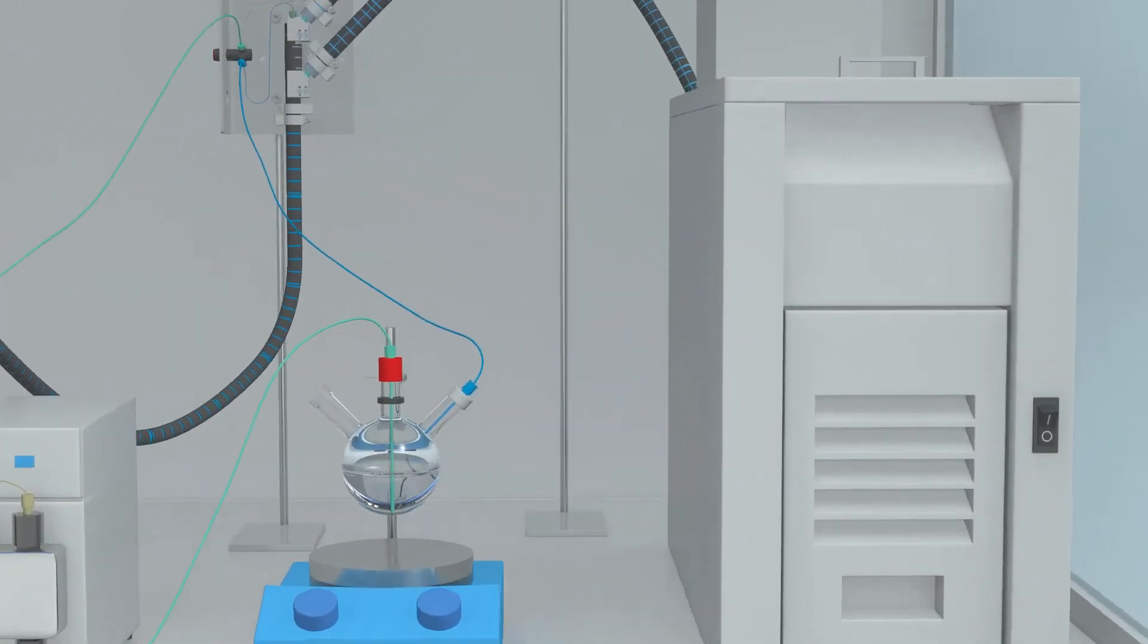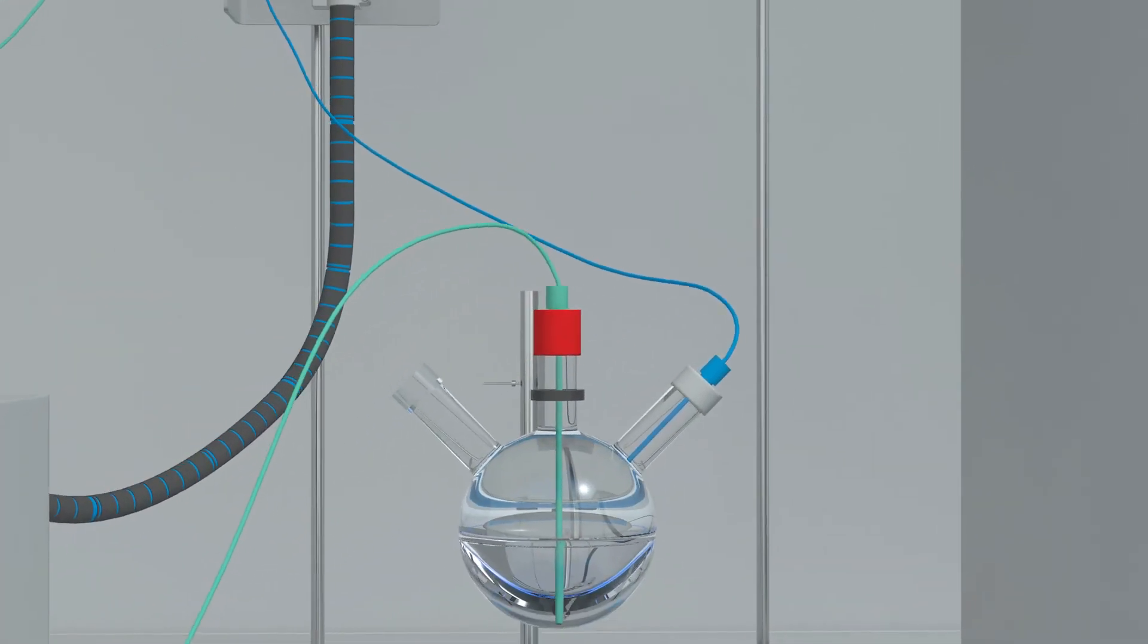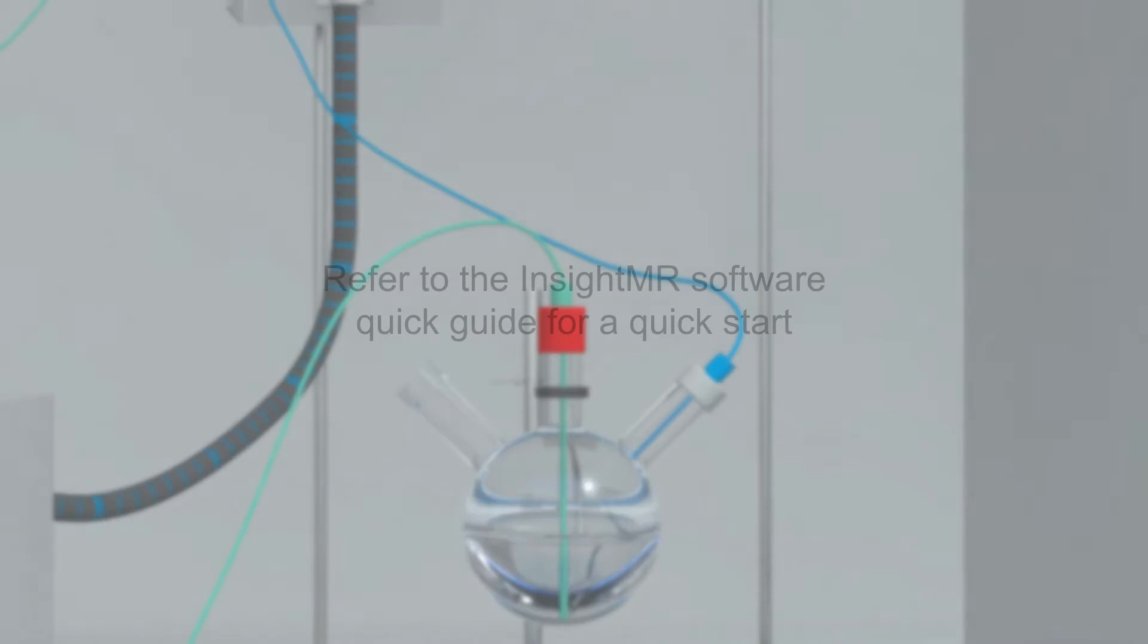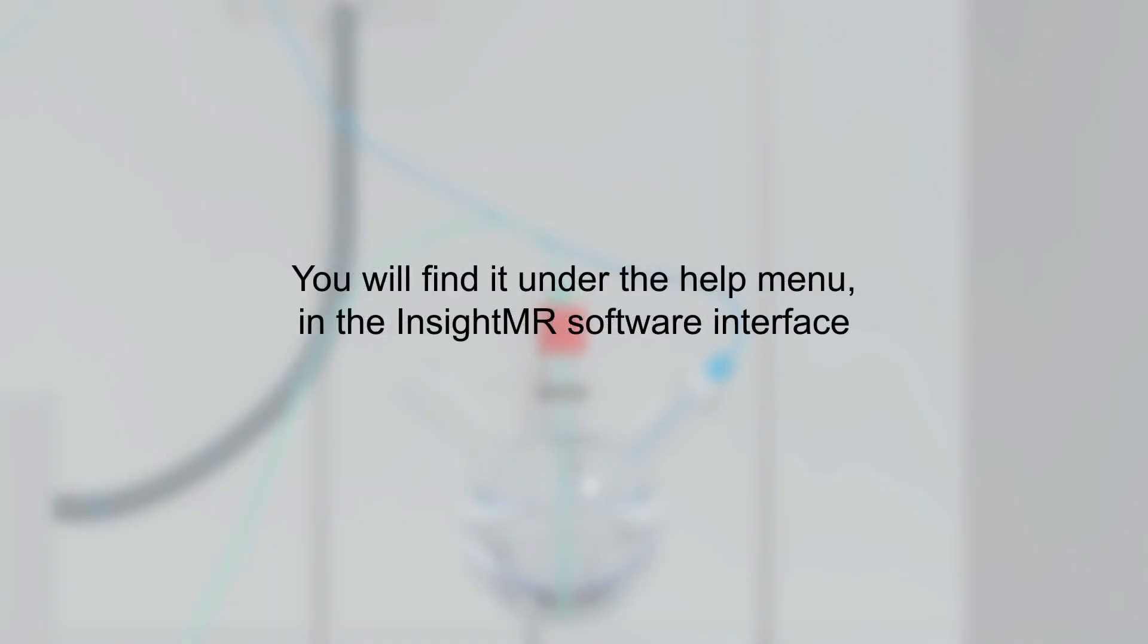During usage it is recommended that you regularly check the liquid levels in the thermostat and also the reactor, simply to make sure that there are no leaks. Refer to the Insight MR software quick guide for a quick start. You will find that under the help menu in the Insight MR software interface.